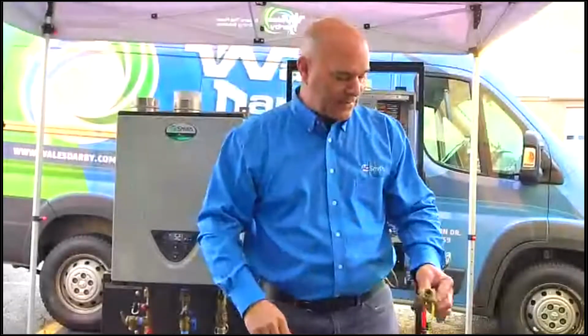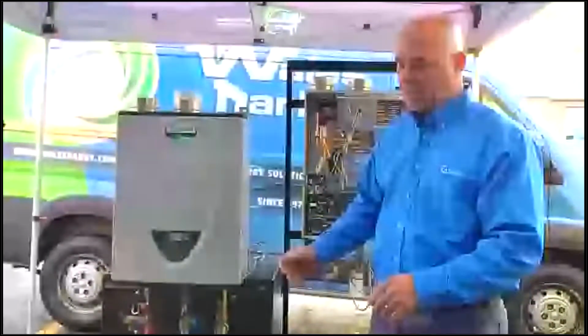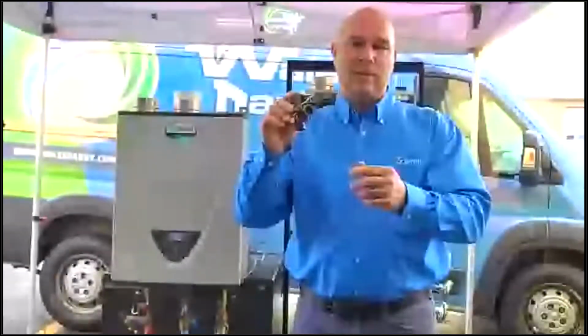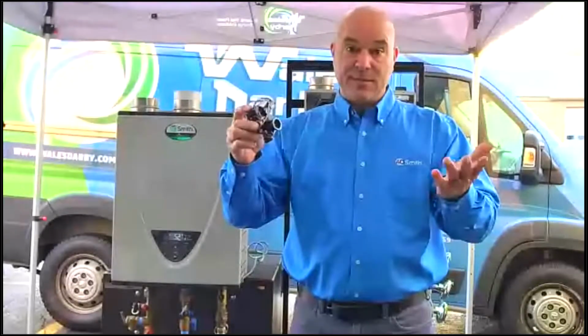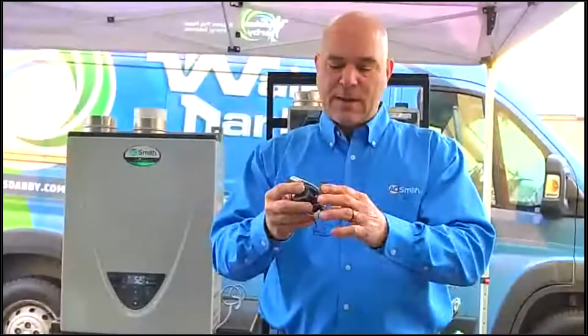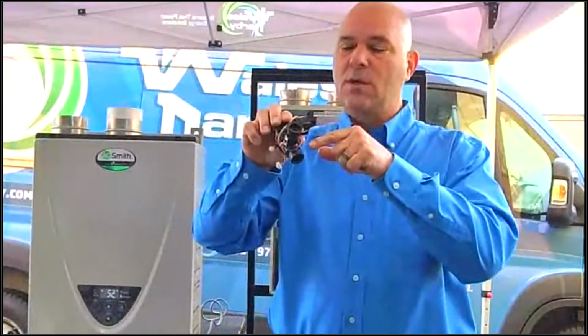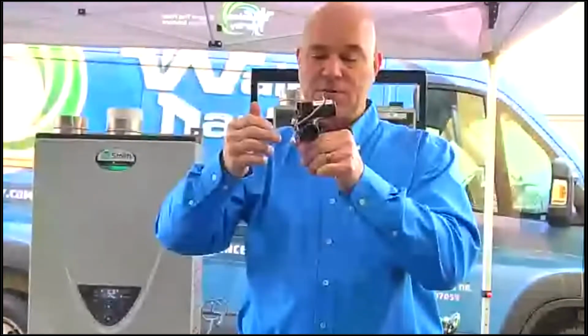That's where our water comes in and enters the heater. The water enters the heater, then hits a flow valve. This flow valve is what's going to gauge the flow, hence its name. This plugs directly into the board. There's a little impeller in there, and as the water runs across the impeller, it rotates. As that rotates, there's a magnetic pickup. So it's a plastic impeller inside of a plastic flow switch. It rotates, and based on how many hits on the magnet, the unit knows the flow rate.